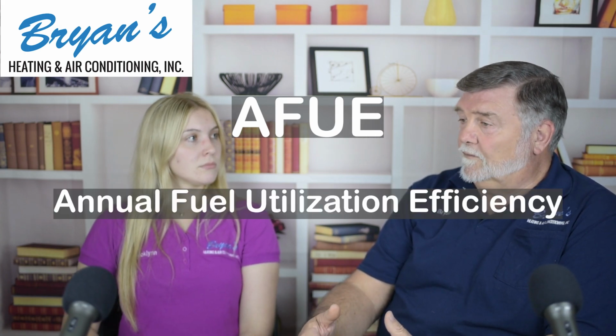So when we have single stage equipment, whether it be a heat pump or an air conditioner, we really need to stick with the size that is required for that particular structure. Now, when we get into gas furnaces, same thing. In previous podcasts, we've talked about furnaces being rated in AFUE, annual fuel utilization efficiency, a percent of efficiency. In order to achieve that efficiency rating, let's say a 96% furnace, those furnaces have to be on and running for a period of time. Think about it, same thing with your car. It's cold outside, you start it up, and the engine's not operating as efficiently in the beginning as it does once it warms up a little bit. Same thing with the efficiency on a gas furnace. So if we oversize a gas furnace and it comes on, only runs for a couple of minutes and shuts off, it never hit its design efficiency and will actually cost the homeowner more money to operate.